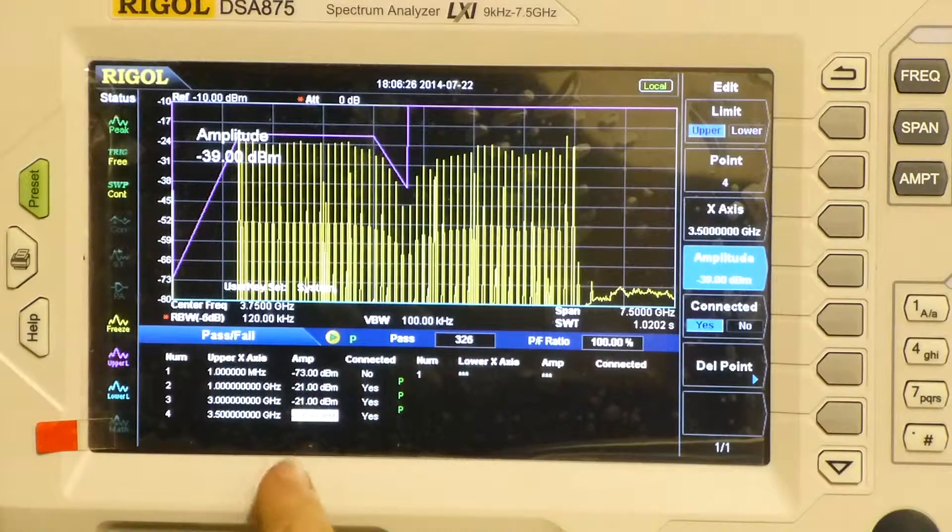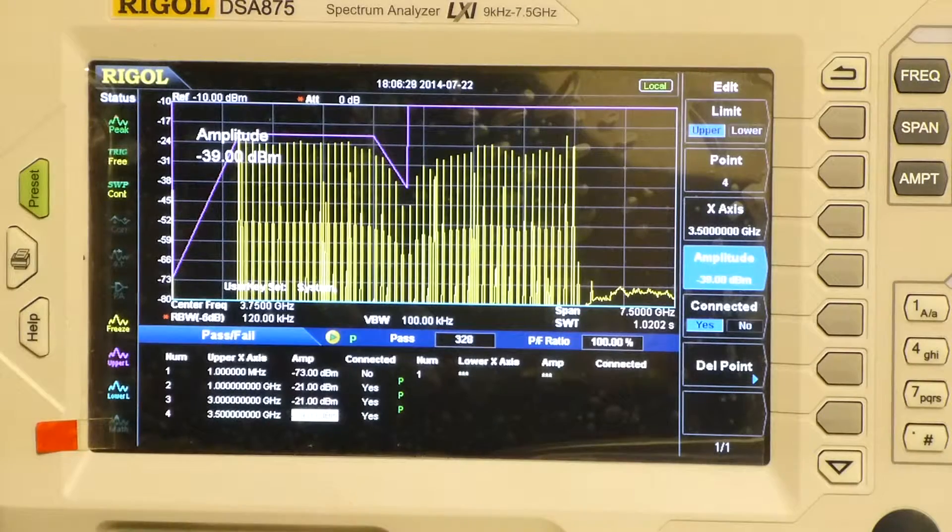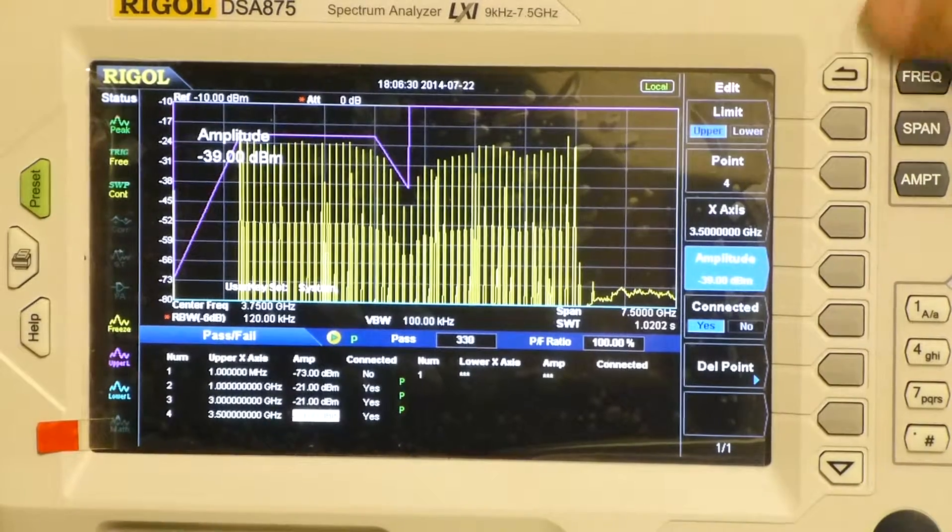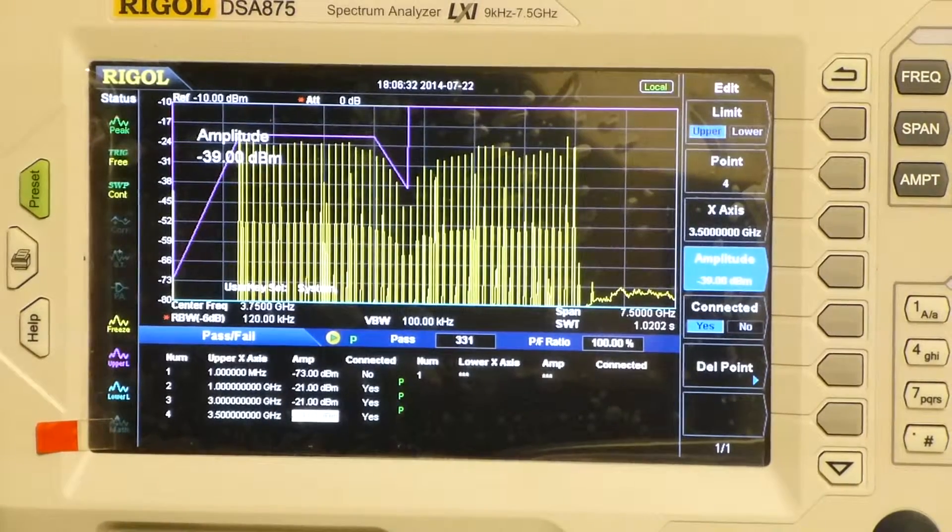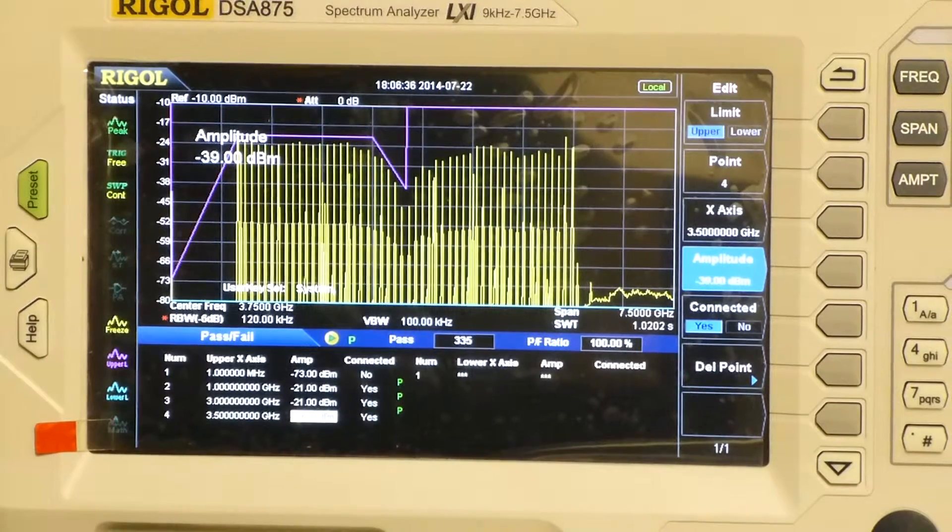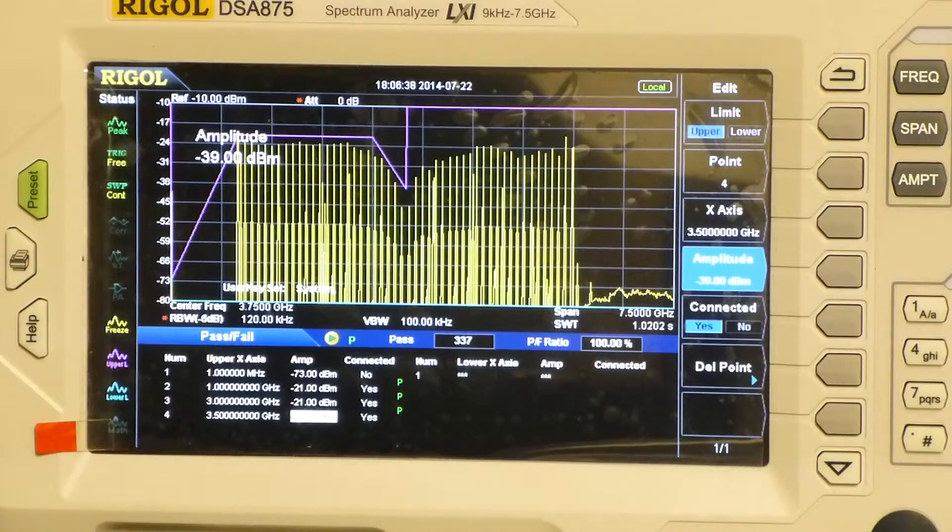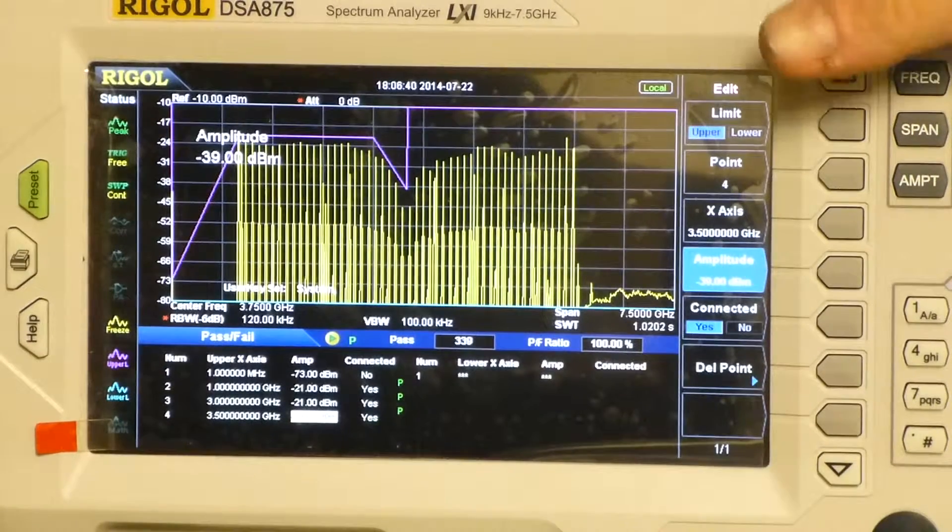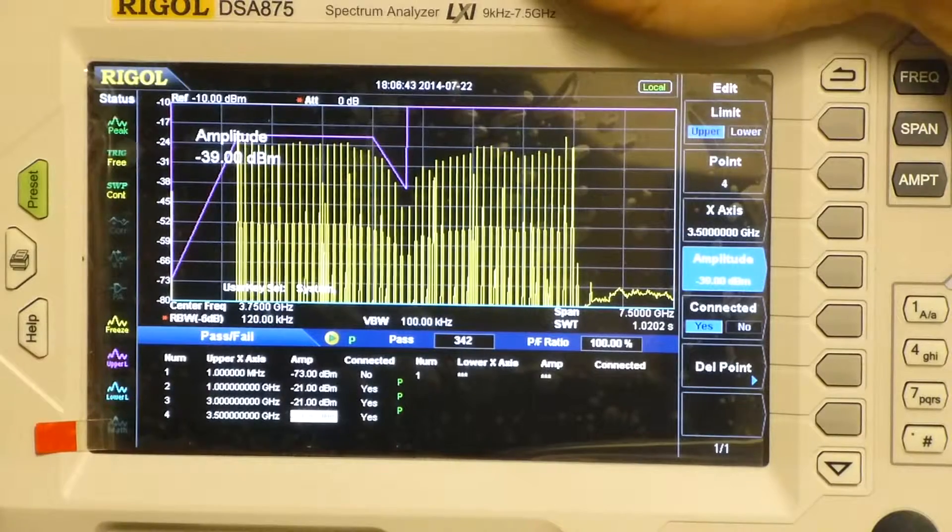You can also save and print out your pass-fail table so that you've got an easy to recall limit line for your pre-compliance emissions standard. So that is how to set up a display line and a pass-fail limit line using the DSA800 series spectrum analyzers to assist your EMI and pre-compliance.